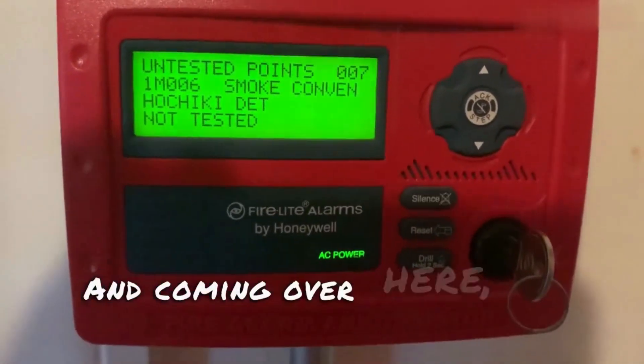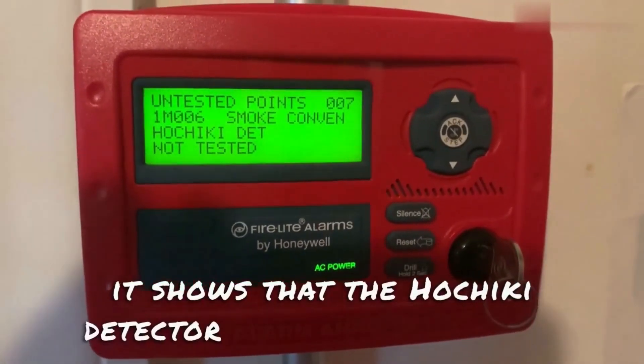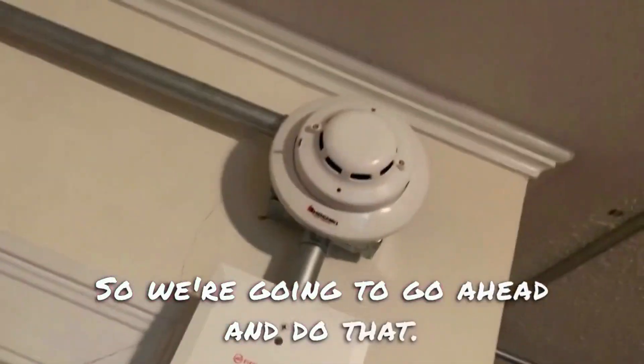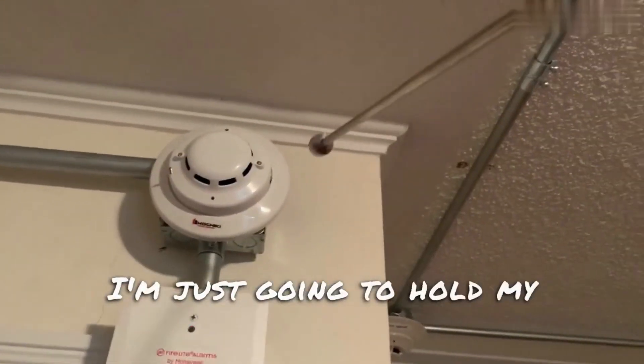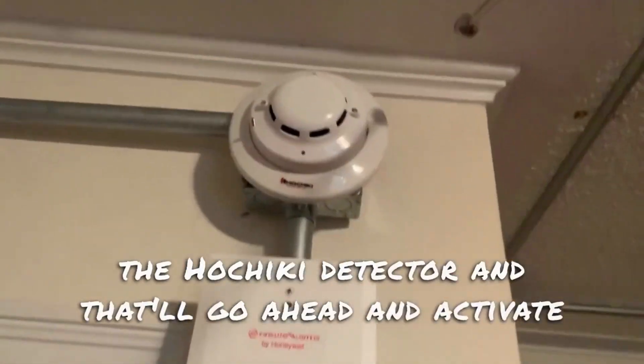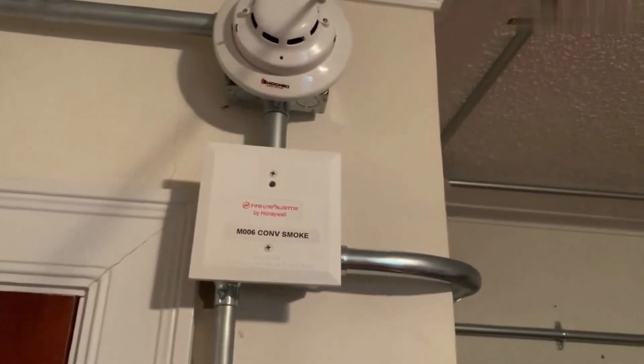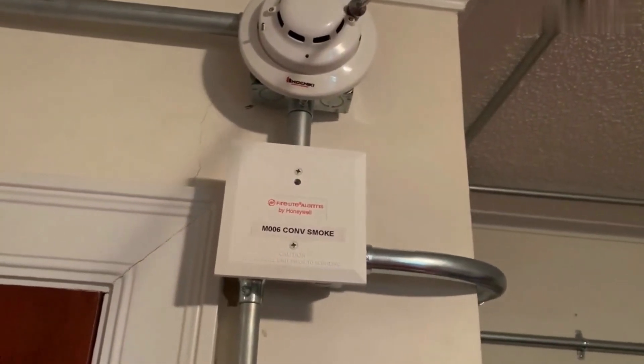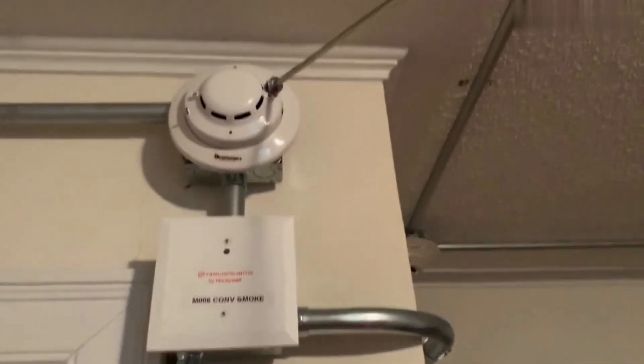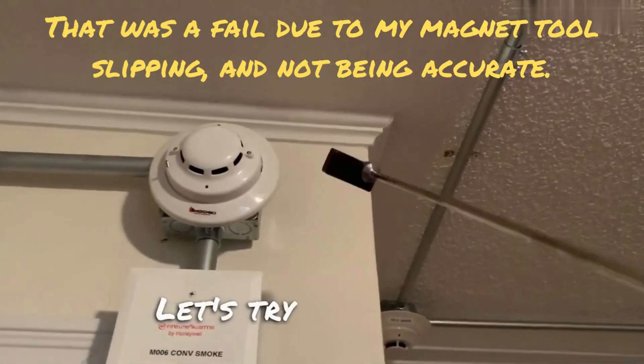Coming over here to the annunciator, it shows that the Hochiki detector has not been tested. So we're going to go ahead and do that. I'm just going to hold my magnet tester up to the Hochiki detector, and that'll go ahead and activate it. Here we go — three, two, one.